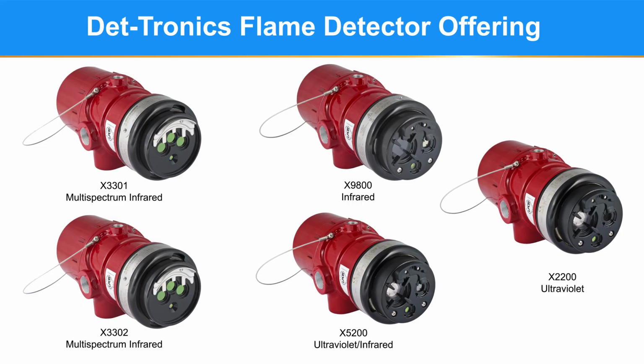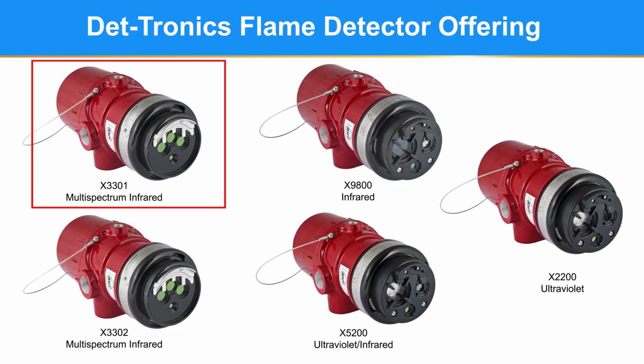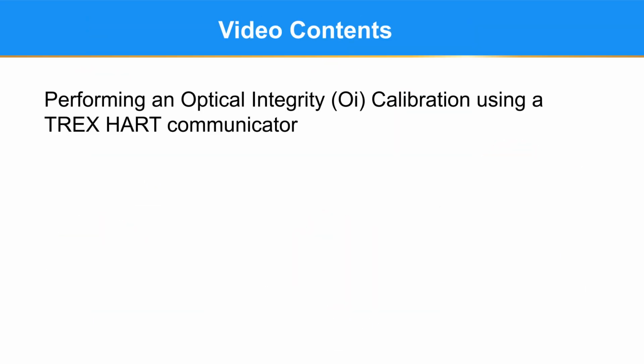The HART protocol is available on all these Det-Tronics flame detectors. The calibration procedures can vary. This video is specific to the X3301 flame detector. The contents of this video are optical integrity calibration and calibration verification.